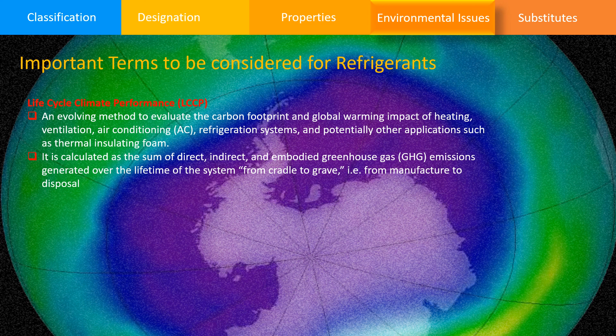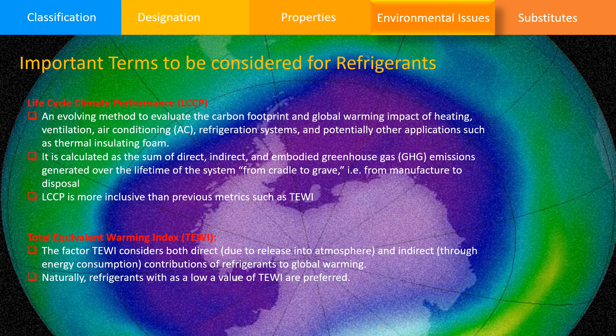What is TEWI? It is total equivalent warming impact. The factor TEWI considers both direct, due to release into the atmosphere, and indirect, through the energy consumption, contribution of the refrigerant to global warming. So it only includes direct and indirect emission, but LCCP includes the manufacturing and disposal cost and other impacts also. Naturally, refrigerants with a low value of TEWI are preferred and they will be preferred in the near future. So what are the substitutes we are going to use?